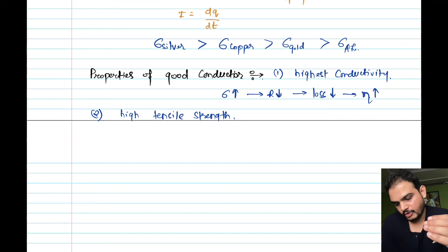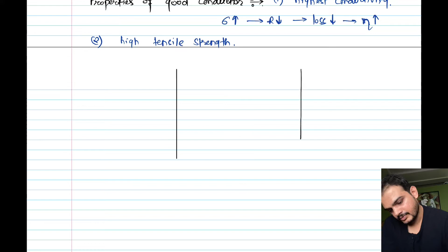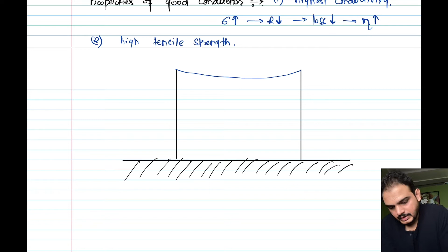The second important property is that our conductor material should have high tensile strength. What is the meaning of tensile strength? For example, we have two towers erected on the land, and in between the towers we have a conductor. This is the first conductor and this is the second conductor. The difference is that the sag in the second conductor is more compared to the first conductor. Why? Because the tensile strength of the second conductor is less.